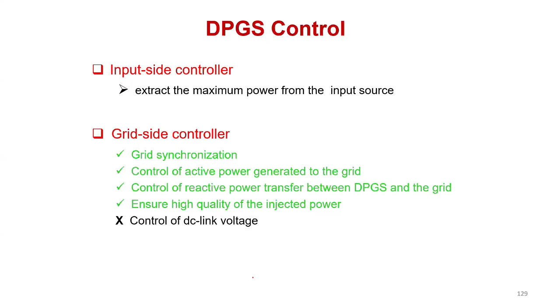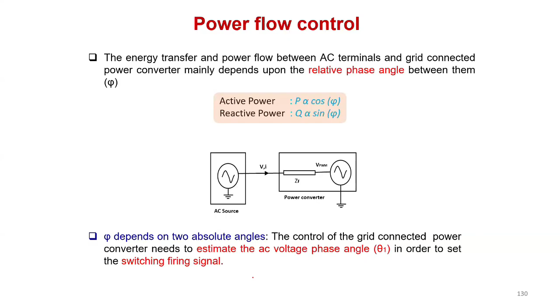So when referring to the fundamentals, the power flow control - the energy transfer and power flow between the AC terminals and the grid connected power converter mainly depends upon the relative phase angle. This phase angle depends on two absolute angles. To control the grid connected power converter, we need to estimate the AC voltage phase angle in order to set the switching firing.